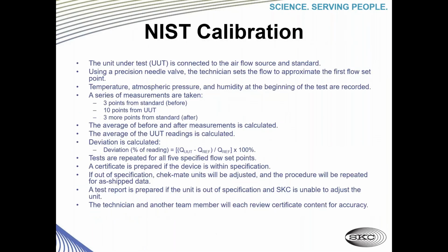Okay, one other question here, I think, Dan, or maybe it's a comment. The 5 measurement series you were talking about for NIST and ISO traceability calibration were not clear. Can you go back to that and maybe clear that up just a little bit? You want me to go to NIST? I'm not sure if the question was a statement. Yeah, we take 5 points, and for certain devices, it's 1 liter, 2 liter, 3 liter, 4 liter, 5 liter. For others, we go lower, like 500 milliliters a minute, 1 liter, 2 liter, 4 liter, 5 liter. But it varies based on the device. That's why I left it vague. I hope that answers the question.